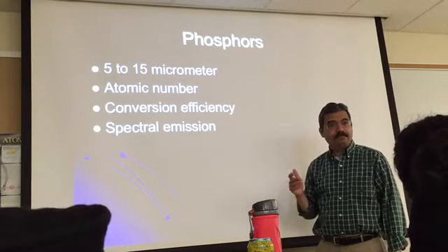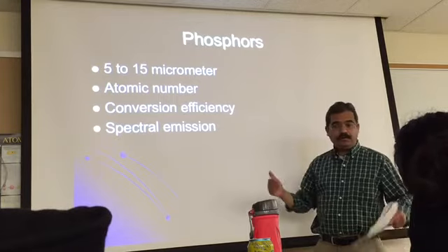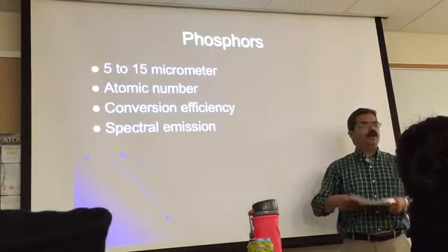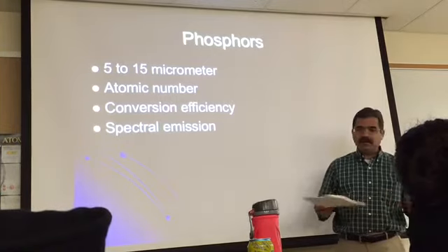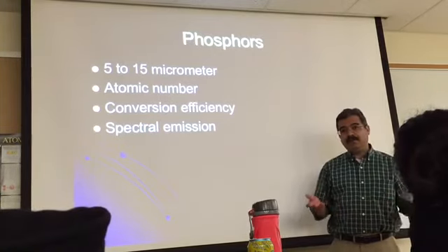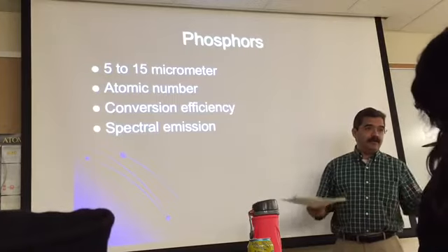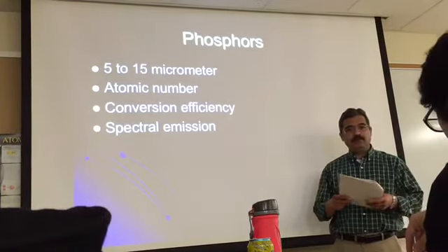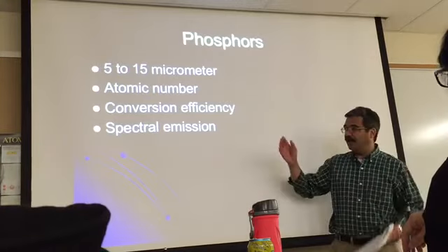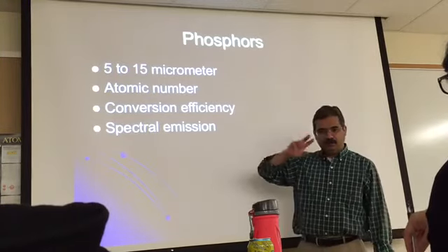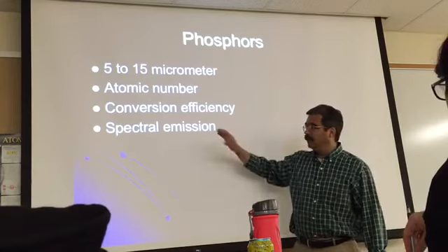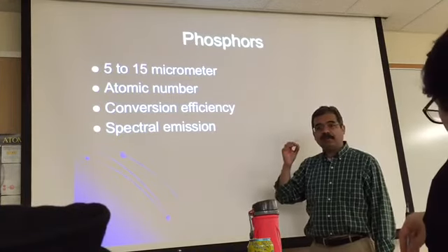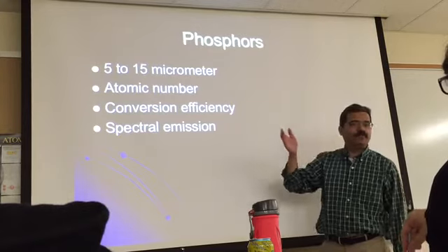Are you with me? If you unknowingly combine one screen with whatever film you found, it might not work. You might not have an image, or it might be a very faint image, or on the other hand, a really dark image. You have to spectrally match the two, the screen and the film. So the spectral emission is very important. You need to be aware of what I am referring to when I say wavelength, guys.